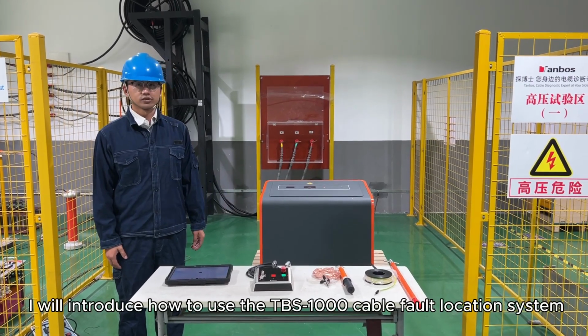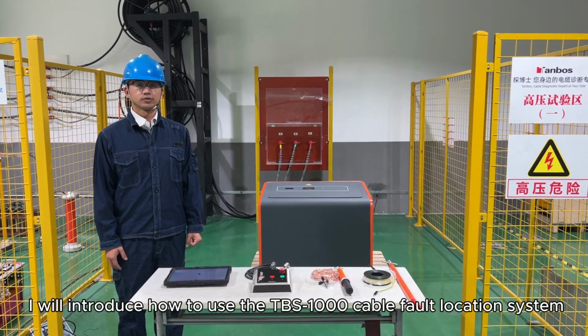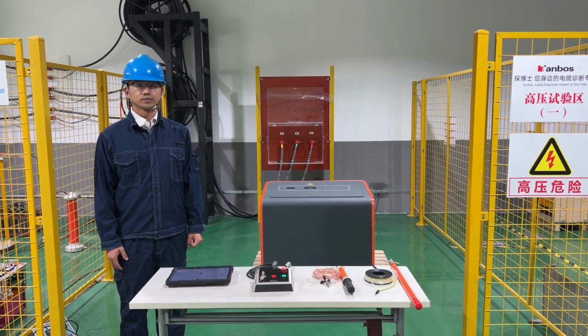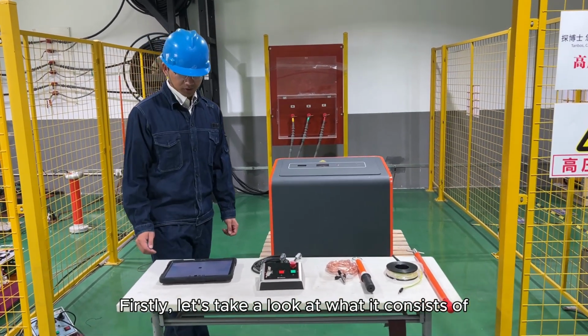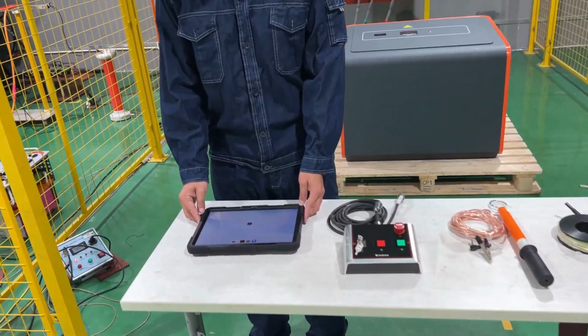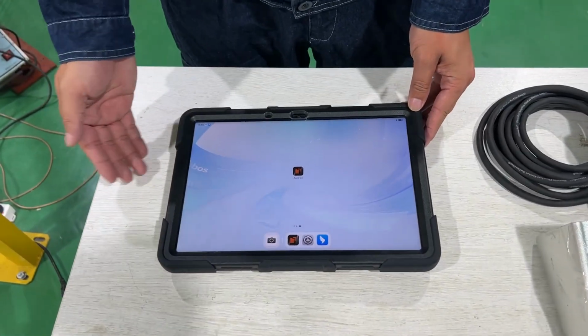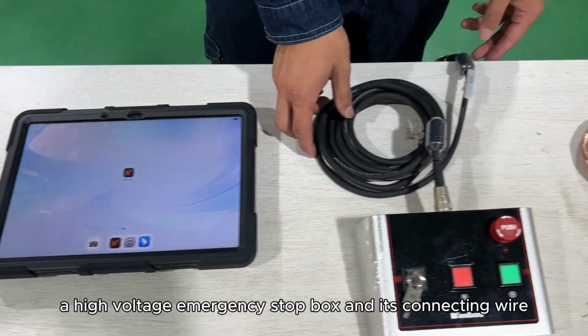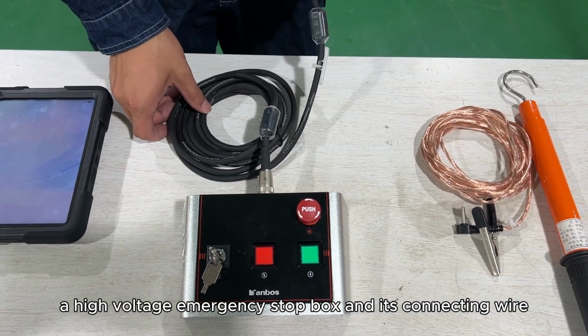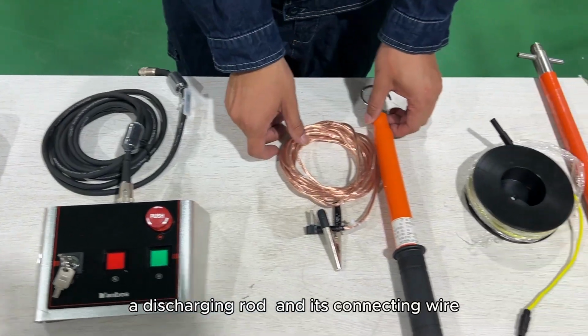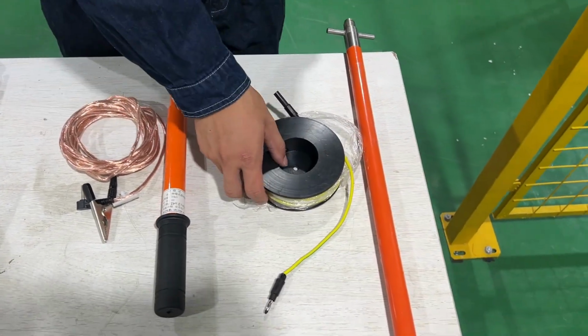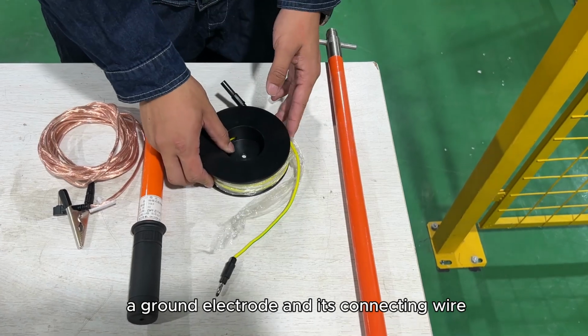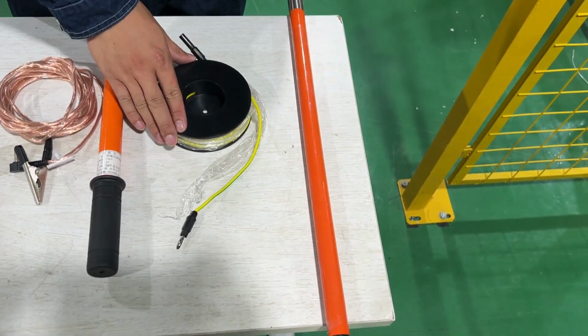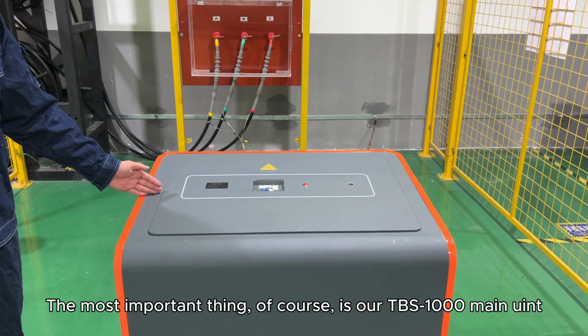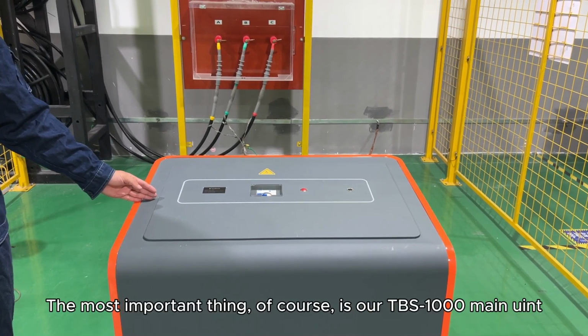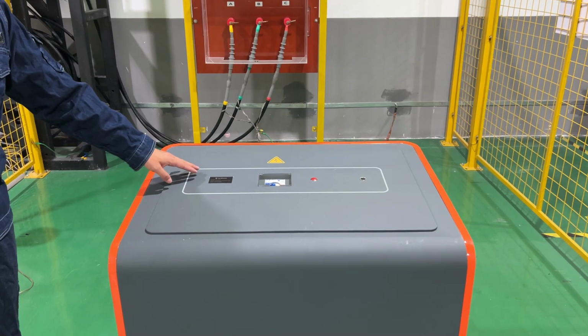Today, I will introduce how to use the TBS-1000 cable fault location system. Firstly, let's take a look at what it consists of. A tablet, a high-voltage emergency stop box and its connecting wire, a discharging rod and its connecting wire, a ground electrode and its connecting wire. The most important thing, of course, is our TBS-1000 main unit.